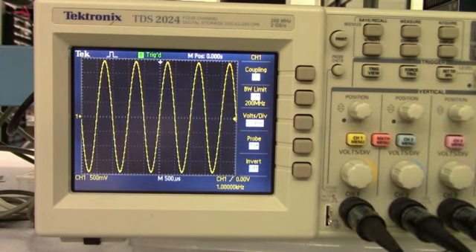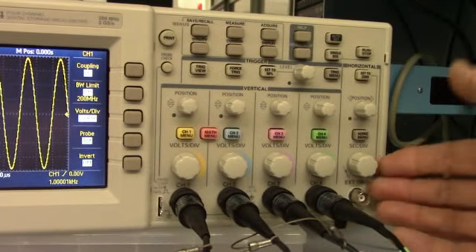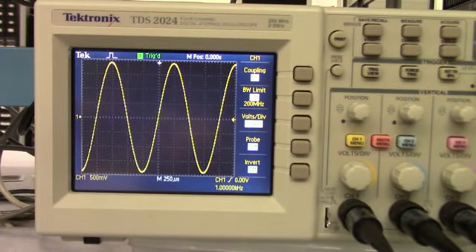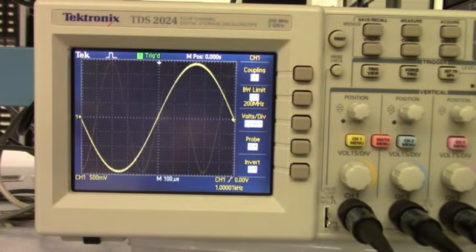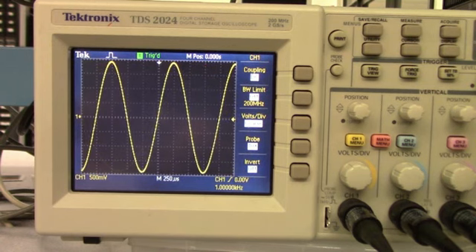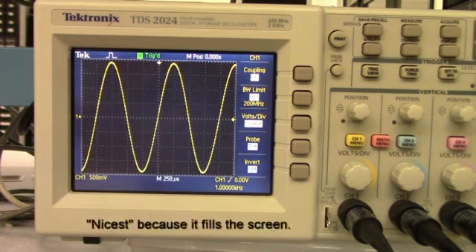possible. Similarly, if we want to change the horizontal time scale, we use the horizontal time base, and as we change the horizontal time base, we go 250 microseconds per division, 100 microseconds per division, 50 microseconds per division. And if it's a repetitive signal, we really don't need to see more than a couple repetitions. So for this signal, 500 millivolts per division and 250 microseconds per division gives us the nicest signal.